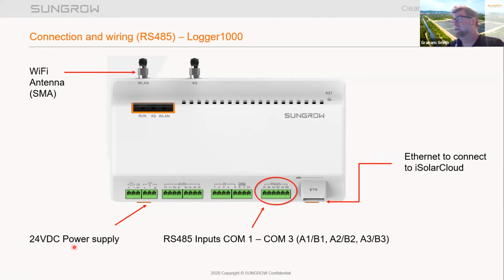A 24 volt DC power supply comes in the box, and that plugs in to this connection here. You can ignore these other ones, and here are your RS485 connections. A1B1, where you connect your inverters, A2B2 for the meter, and there's a spare which you can use if you're connecting like a weather station or something like that. But in most cases, they'll just use the A1B1, A2B2. We also refer to these as COM1 and COM2 when we're doing the commissioning. Oh, and it just mounts on a DIN rail, so you can put it in an enclosure if you want.